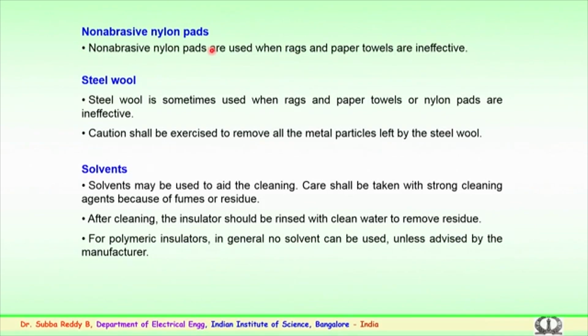So, some solvents may cause fumes, or the residue left on the surface could again cause problems to the surface of the insulators. So, picking the solvents is also an important aspect of cleaning. After cleaning with the solvents, the insulator should be rinsed with clean water to remove any residue left by the solvents on the surface of the insulators.